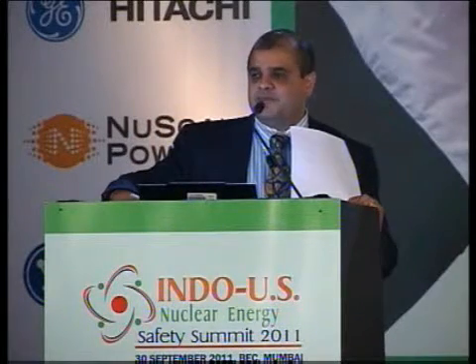However, as a defense in depth measure again, the ESBWR containment is naturally inert, and PARs, or passive autocatalytic recombiners, are provided for hydrogen removal, as well as a high pressure rated vent pathway for containment with airspace. There's also the core catcher, or the BIMAC, as we refer to it, the basemat internal melt arrest coolability device, which is located within the primary containment, precisely with the objective of containing the corium should it make its way through the RPV and minimizing the core concrete interactions, so preventing a severe accident.